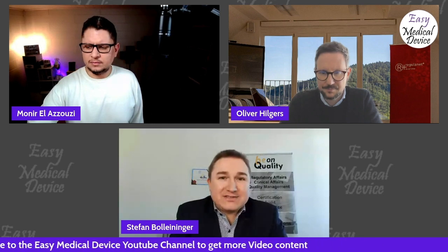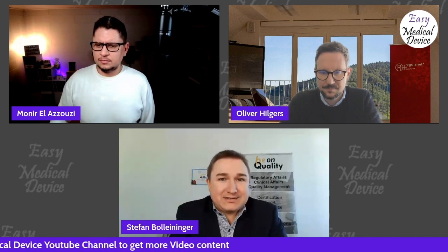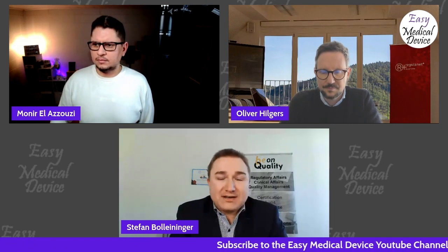That depends on what standards you're using and how you do it. So whether it's Class 1 or Class 2A, it just makes it different in the registration or in the clearing process with a notified body. But you deliver the quality and the functionality as well as the correctness of documentation, and that's equal on both classes.